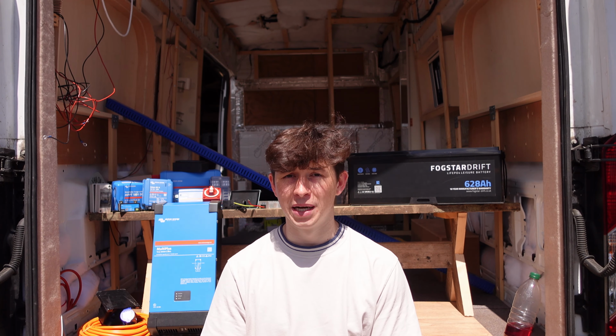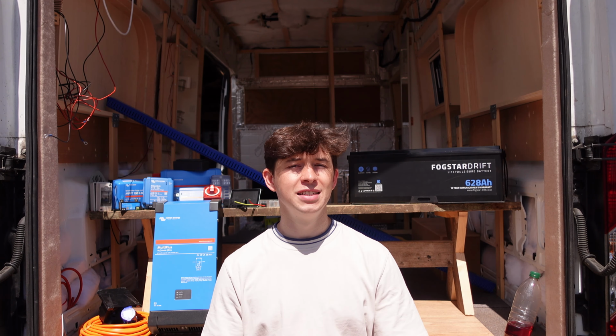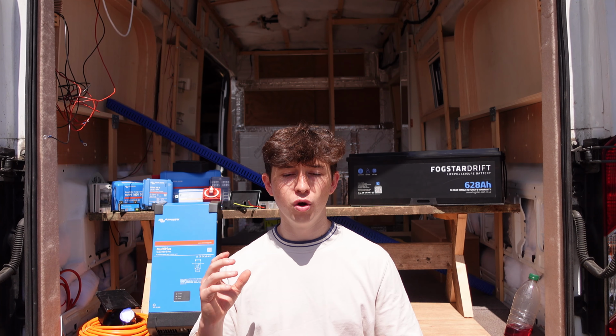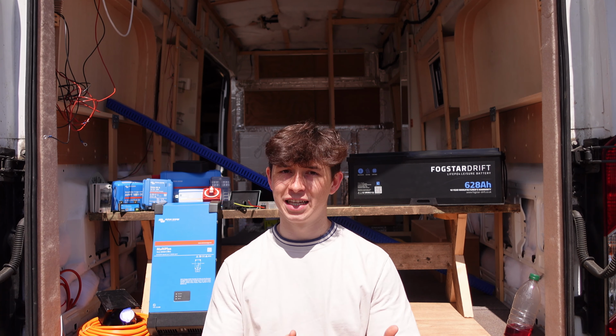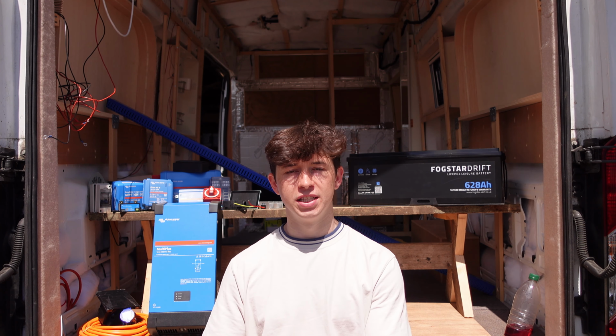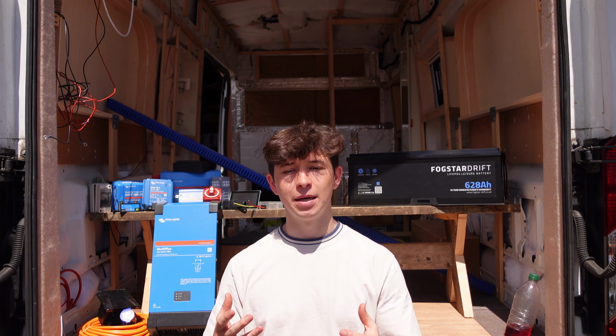In general, this is less favourable, as a series arrangement can leave the batteries more susceptible to becoming imbalanced, because the two batteries are not forced to remain at the same voltage and state of charge. A single battery's management system is usually able to keep its own cells balanced, and there are some more sophisticated batteries able to communicate with one another and ensure all the cells in the battery bank are balanced.